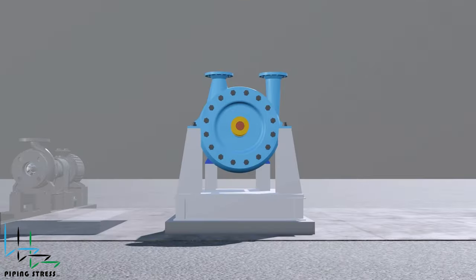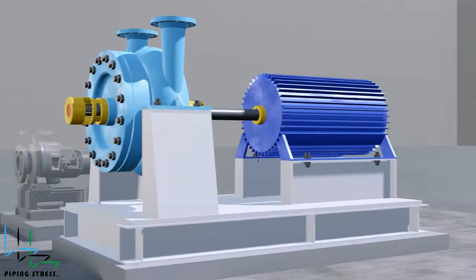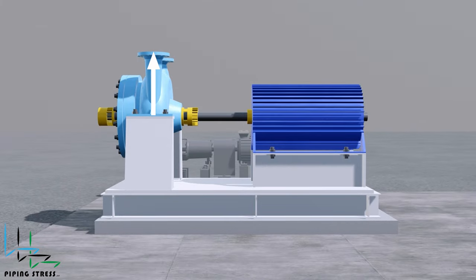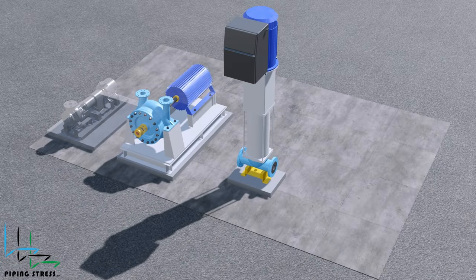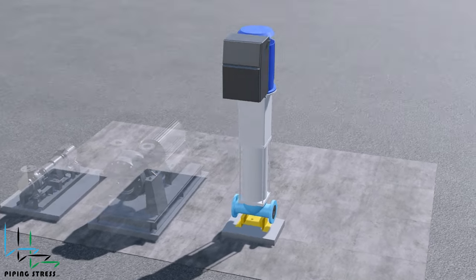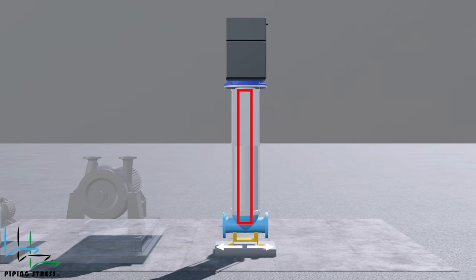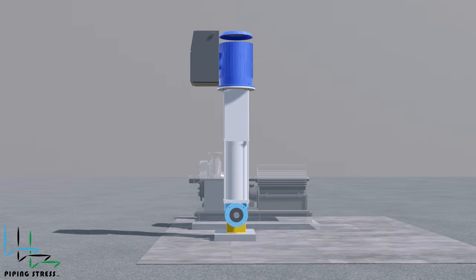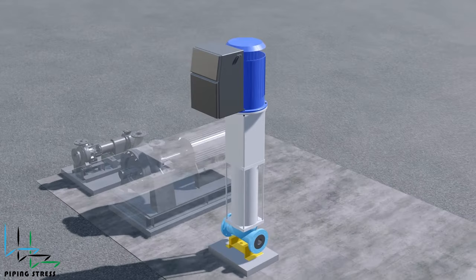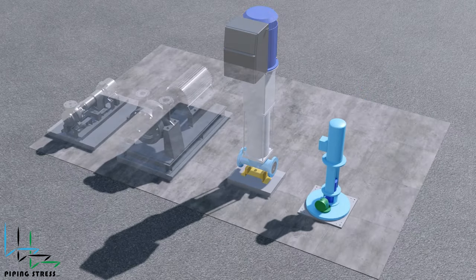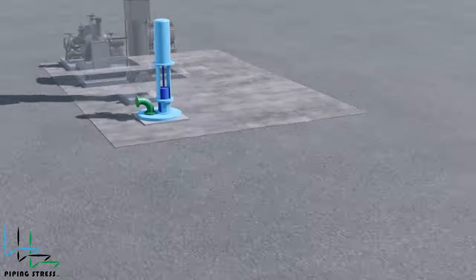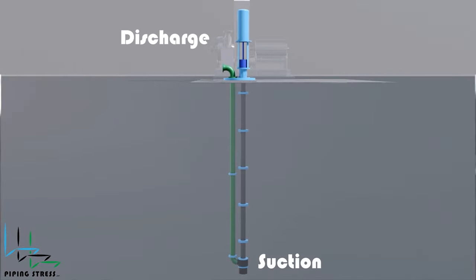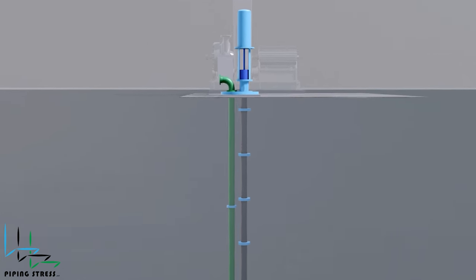The thermal expansion directions of between bearing pumps vary from each other. For a radially split pump, this is the expansion direction. Vertical inline overhung pump expansions are perpendicular to the shaft. For vertical suspended pumps, expansion is valid only for the discharge nozzle, as the suction nozzle is dipped into the basin.